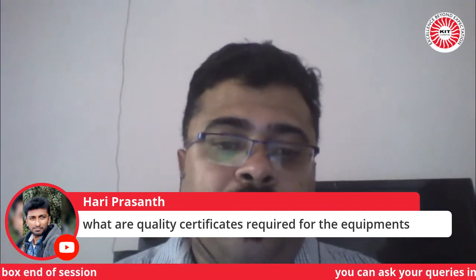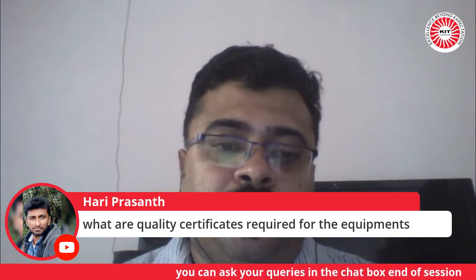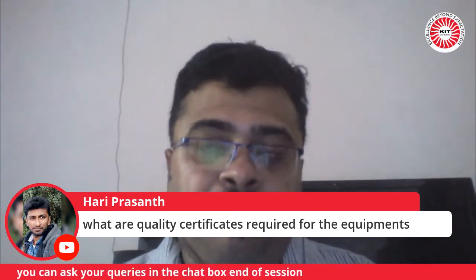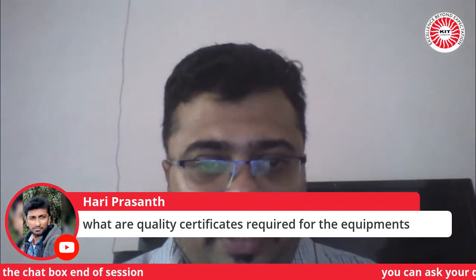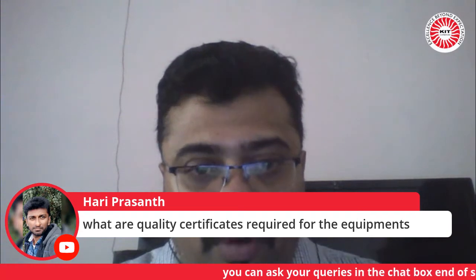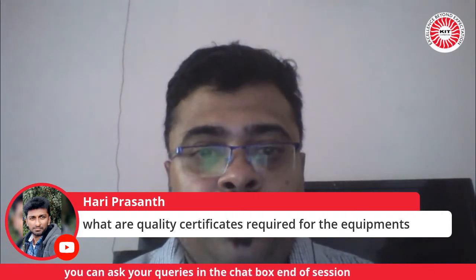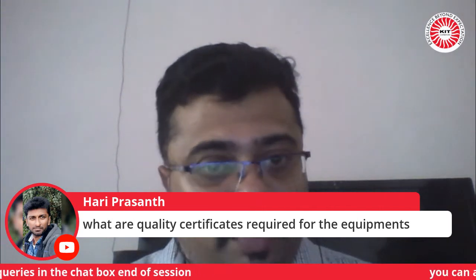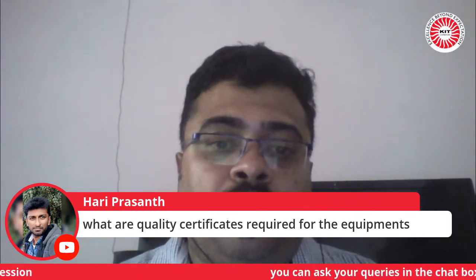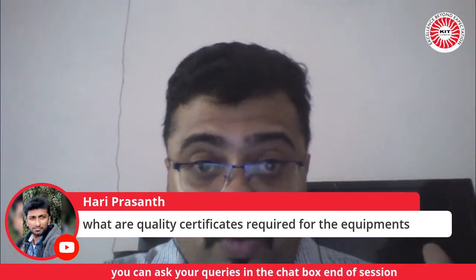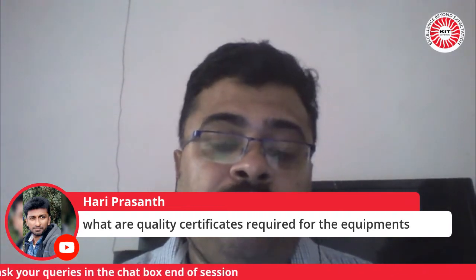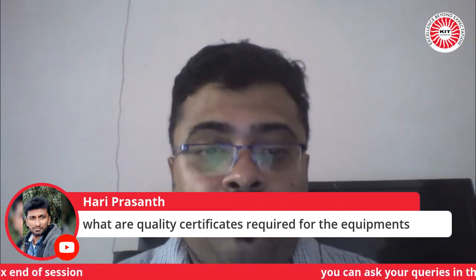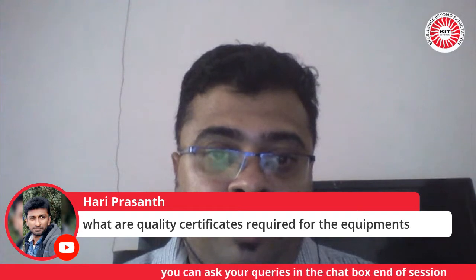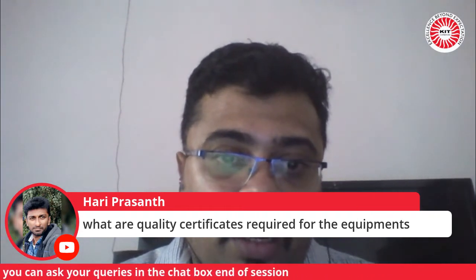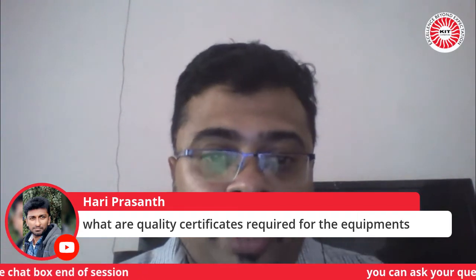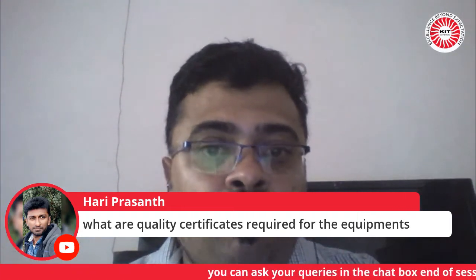Thank you. Quality certificates required for equipment depend on the device, say any ECG or ventilator. When buying new equipment, it comes with a safety testing certificate as well as a performance testing certificate. Apart from that, with respect to international standards, if I'm a ventilator manufacturer making a ventilator for the market, I need to come out with a CDSCO quality certificate declared by the government body.